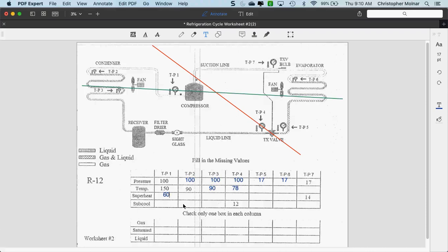So you converted the pressure to temperature at my condensing point. Okay. That gives you my condensing temperature. Think back to one of the first things I said when we were talking about gauges. Do I really care about the pressures? The pressures are cool to give me the temperature. And the pressure only tells me the temperature of 2 points in the system.